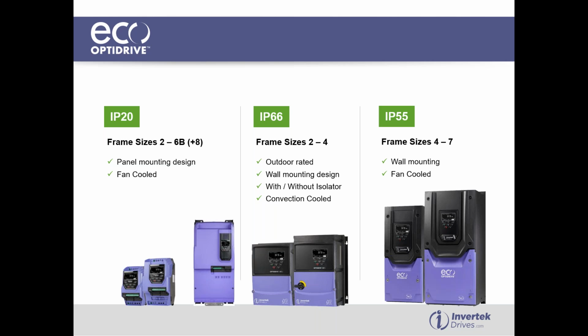The IP66, again, outdoor rated, so it's a wall mounted design. We can have it with or without an isolator. And these are convection cooled, so there's no heatsink fan on these. Then we have the IP55, again, wall mounted type units, and they are fan cooled. So you have heatsink fans on the unit to push the air through to keep the units cool while they're running under load.